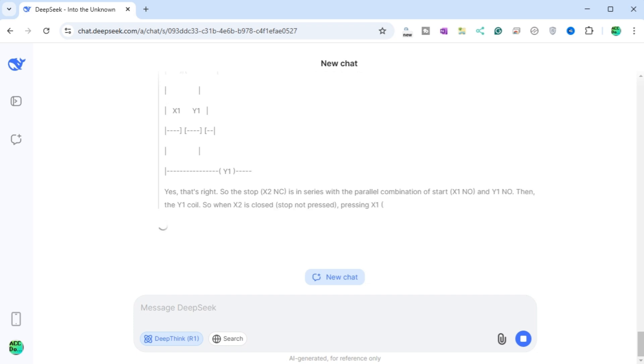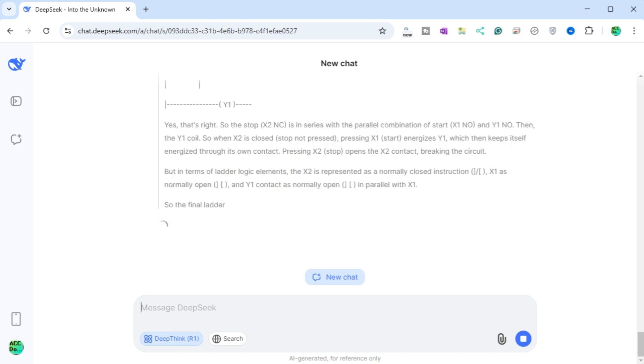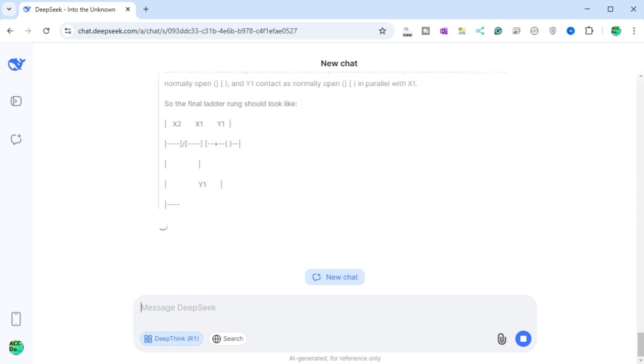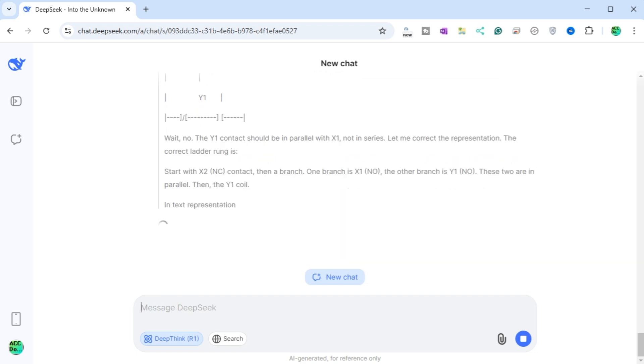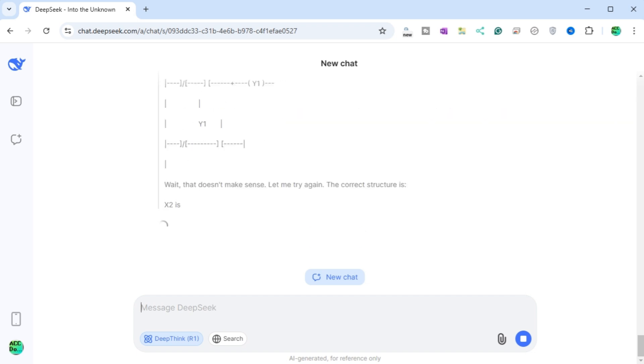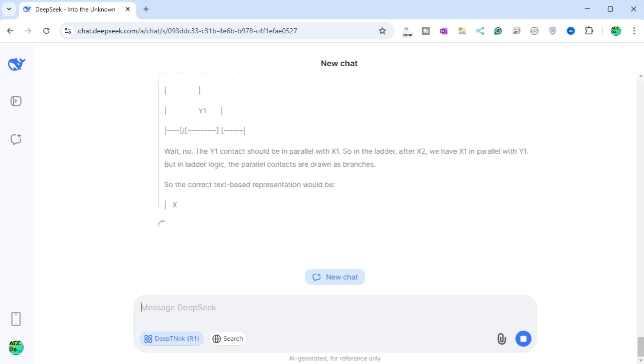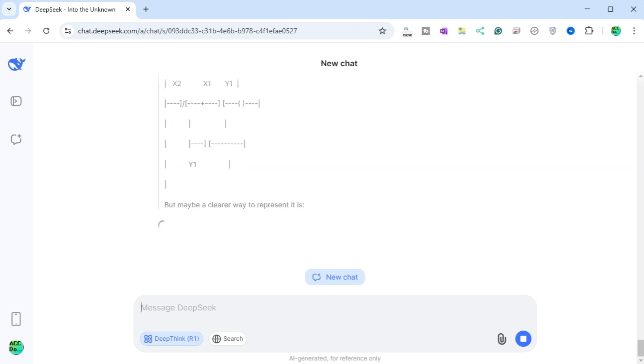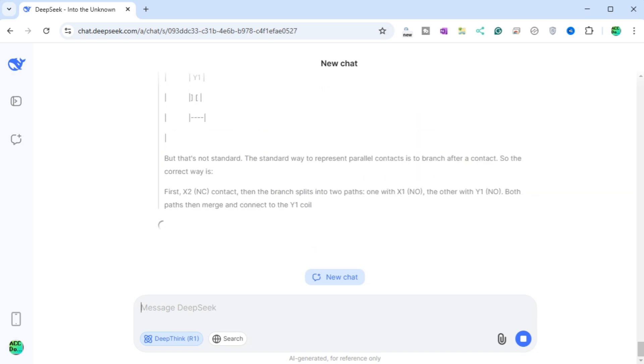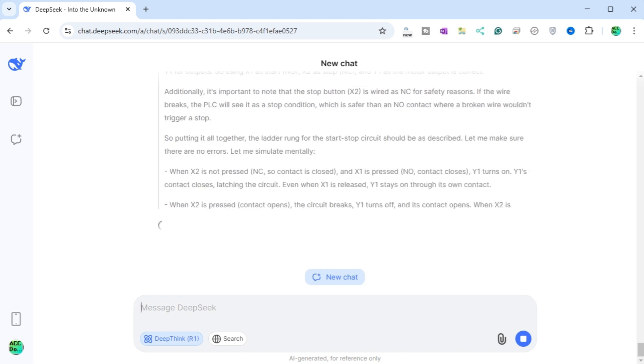DeepSeek also notes that for the BRX PLC, inputs are mapped as X0, X1, etc., and outputs as Y0, Y1, so using X1 as start (NO), X2 as stop (NC), and Y1 as motor output is correct. The stop button X2 is wired as NC for safety — if the wire breaks, the PLC sees it as a stop condition, which is safer than an NO contact where a broken wire wouldn't trigger a stop. The Y1 contact is in parallel with X1. When X2 is closed, either X1 or Y1 can keep Y1 energized. Pressing X1 energizes Y1, which stays on by its own contact; pressing X2 de-energizes Y1.